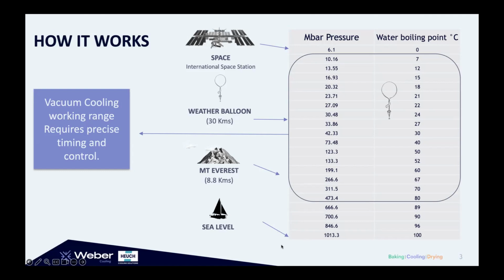If you go lower in pressure, so if you go up to Mount Everest, pressure will be lower and you will be able to cook or boil water much faster. You can go down in pressure to 6 millibar, which will equal 0 degrees. So this table is actually what I always call the magic table, and this is what's happening in the vacuum cooling process.